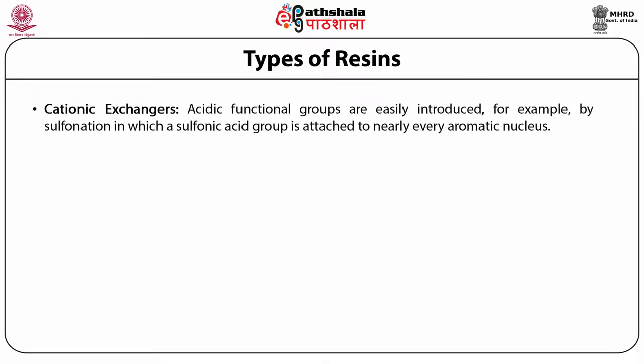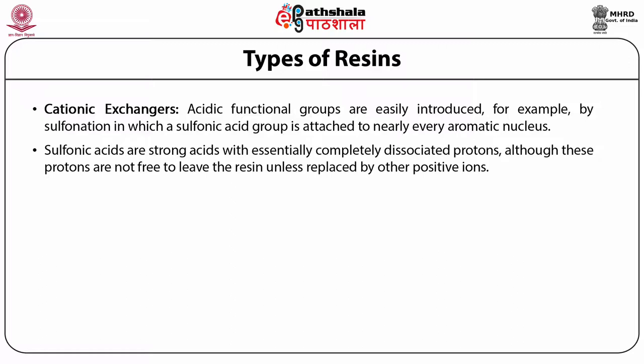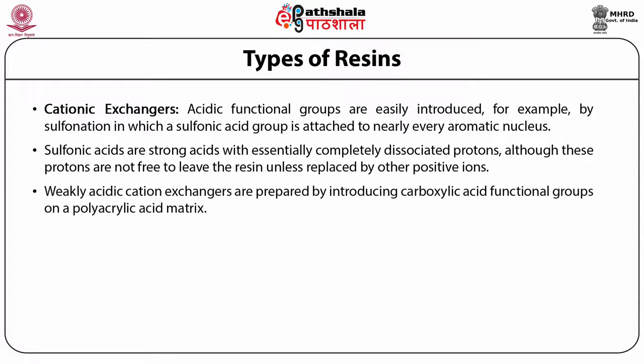Acidic functional groups are easily introduced, for example by sulphonation, in which a sulfonic acid group is attached to nearly every aromatic ring. Sulphonic acids are strong acids which are essentially completely dissociated, yielding protons, although these protons are not free to leave the resin unless replaced by other positive ions. Weakly acidic cation exchangers are prepared by introducing carboxylic acid functional groups on a polyacrylic acid matrix. The total number of equivalents of replaceable protons per unit volume of resin determines the exchange capacity of the resin. For weak ion exchange resins, the capacity is a function of pH.